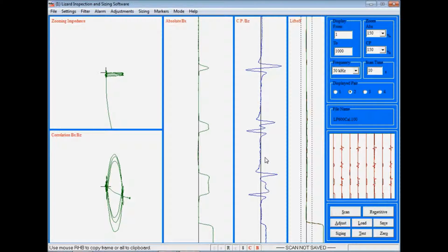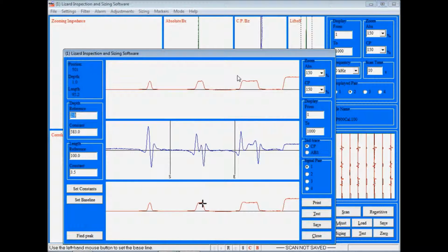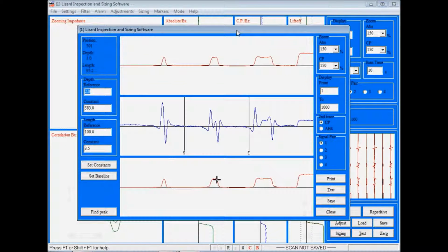This is the LP600 probe, and what we'd like to do is tell the system that this is a 2mm amplitude. So if I click into sizing, now the difference with the Lizard system as opposed to other systems on the market is that in order to generate the depth information from the data, we do not need to know the length of the defect. Now this is different to other AC field measurement suppliers.